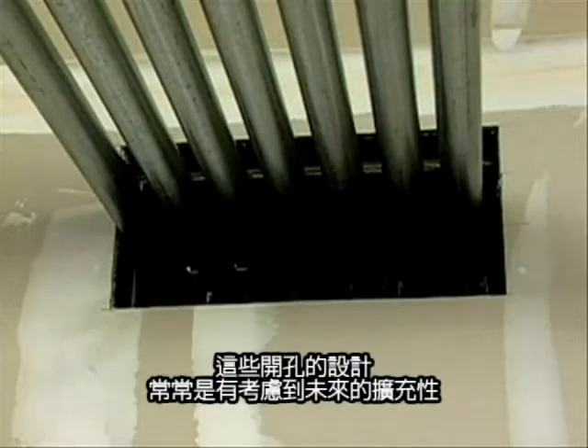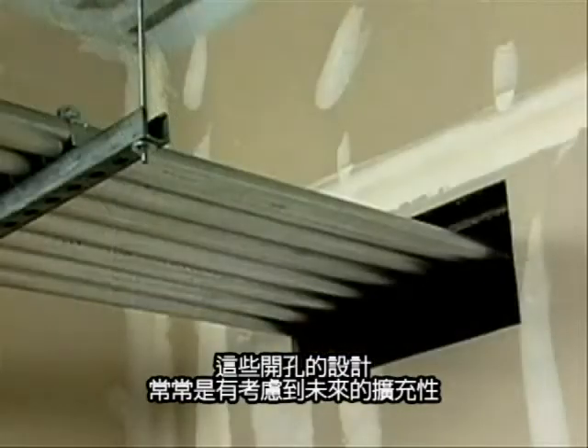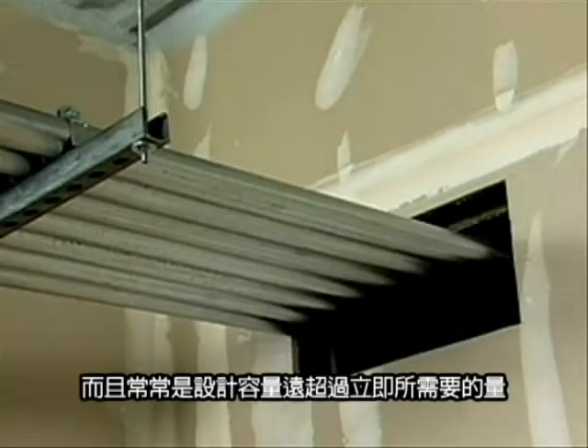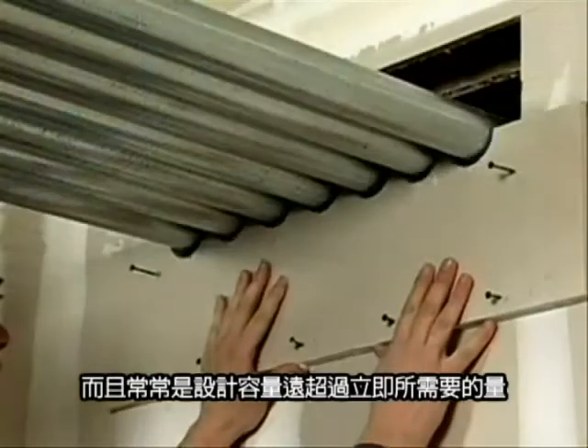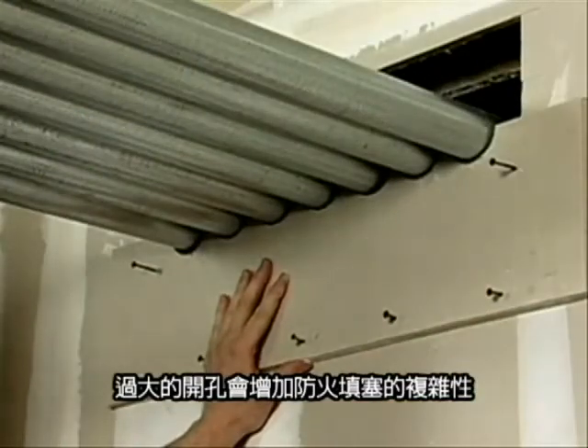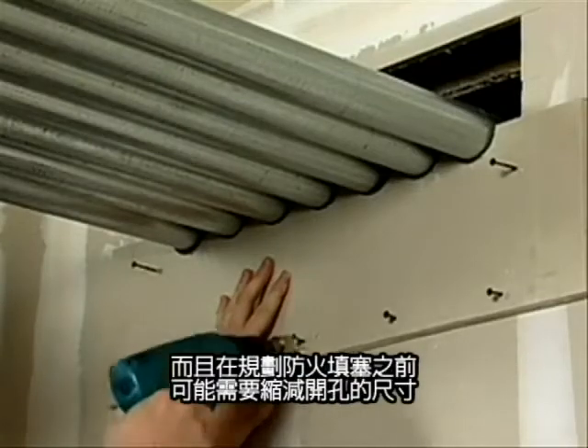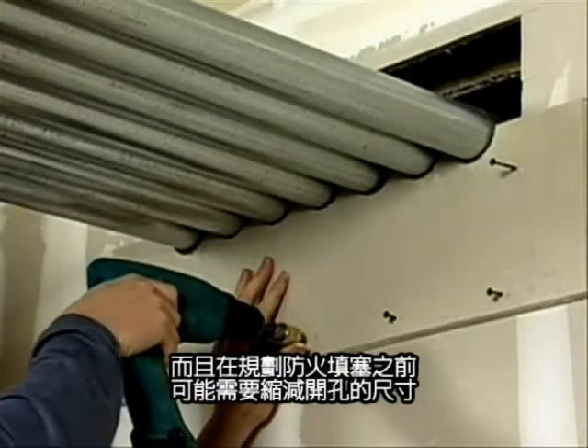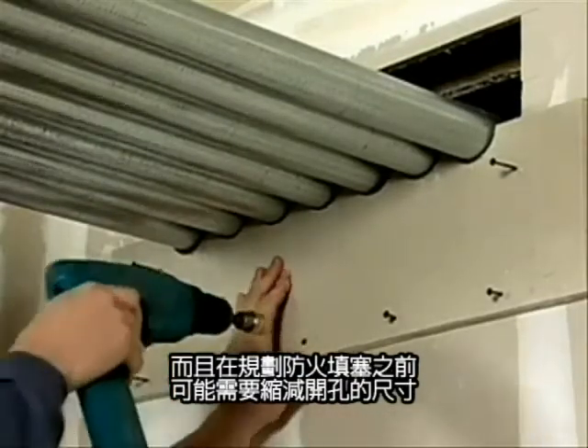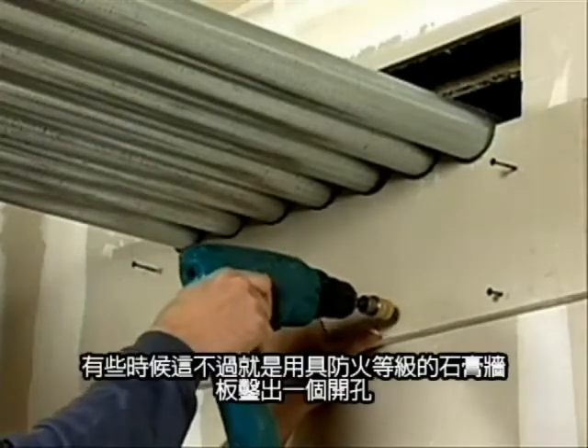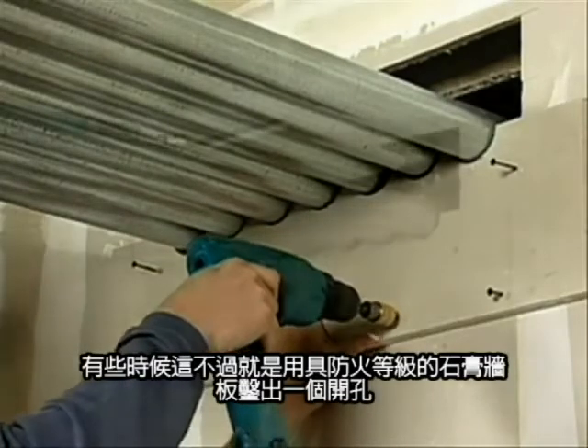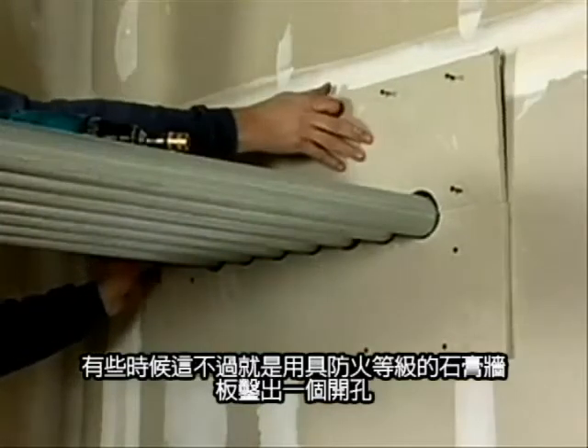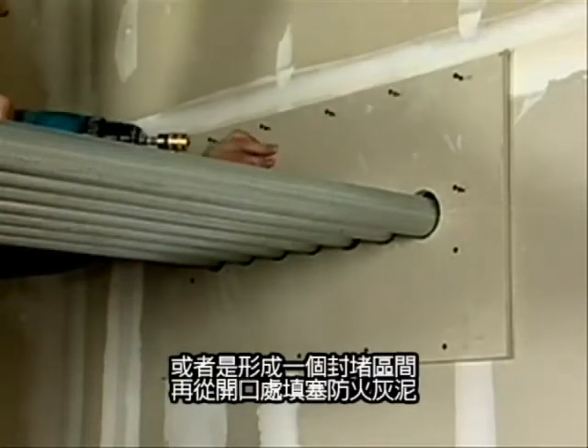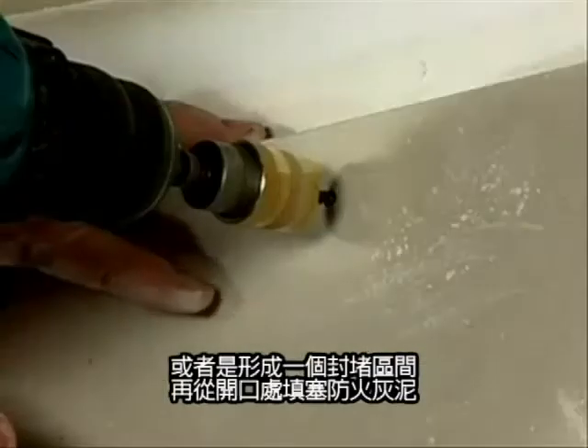These openings are often designed with future capacity in mind and are frequently far larger than immediately necessary. Excessively large openings can complicate fire stopping and may require a reduction of the opening size before the fire stop itself can be addressed. Sometimes this is simply a matter of scabbing down a hole using layers of fire-rated gypsum wallboard or forming a dam and pouring fire stop mortar into the opening.